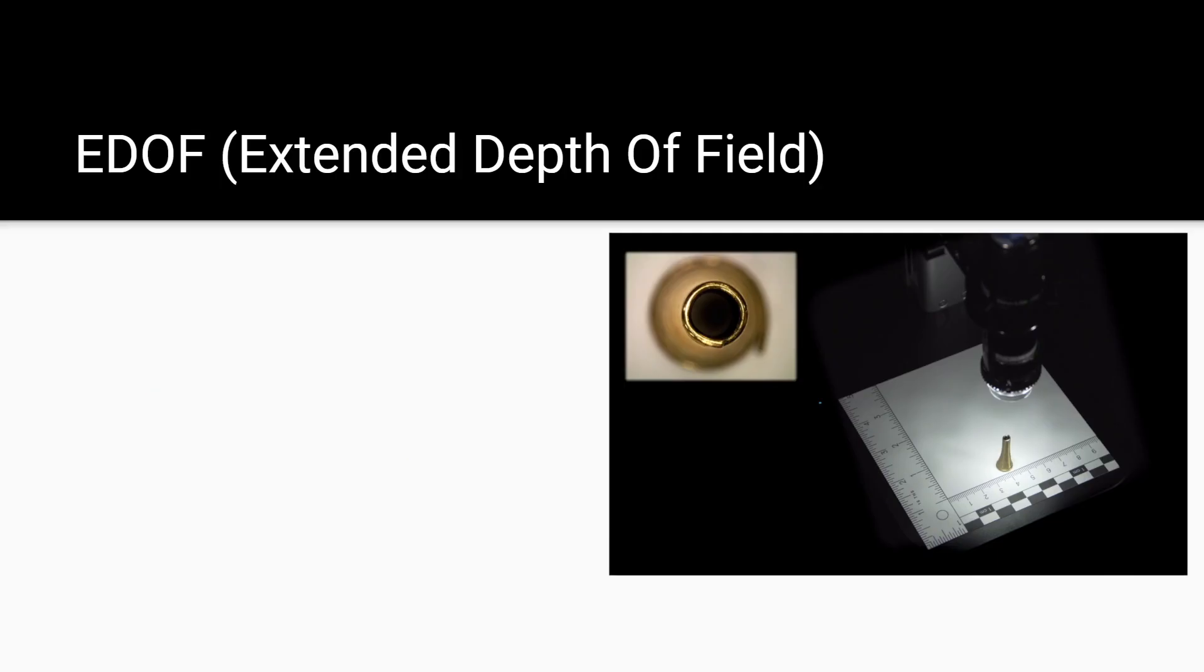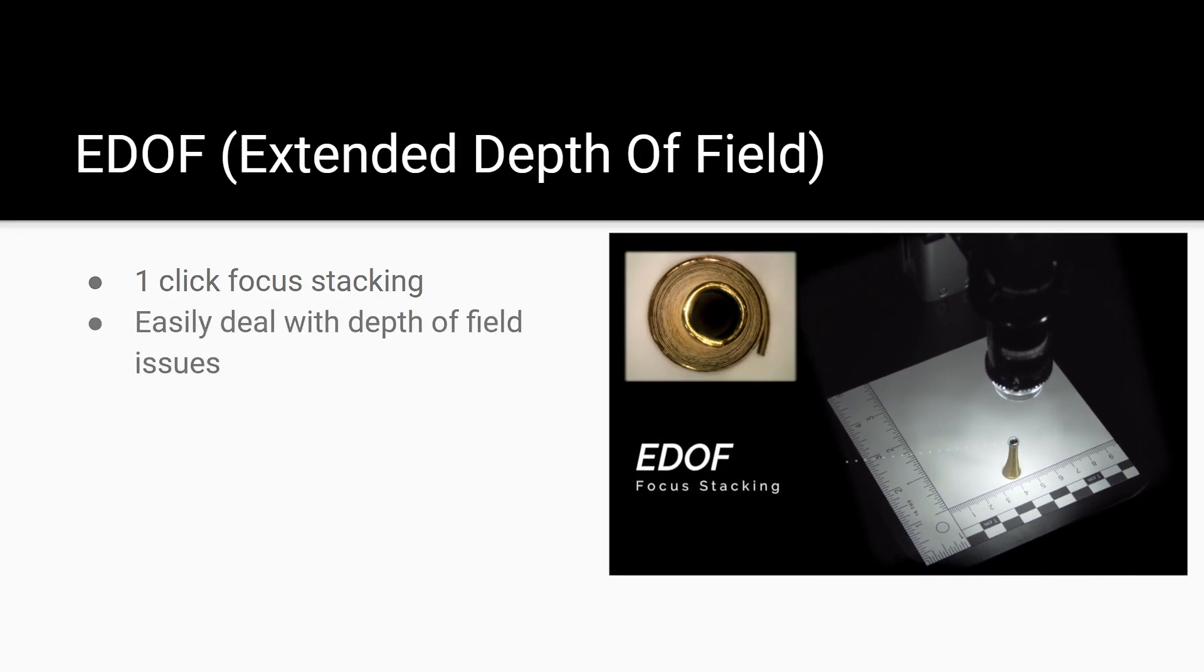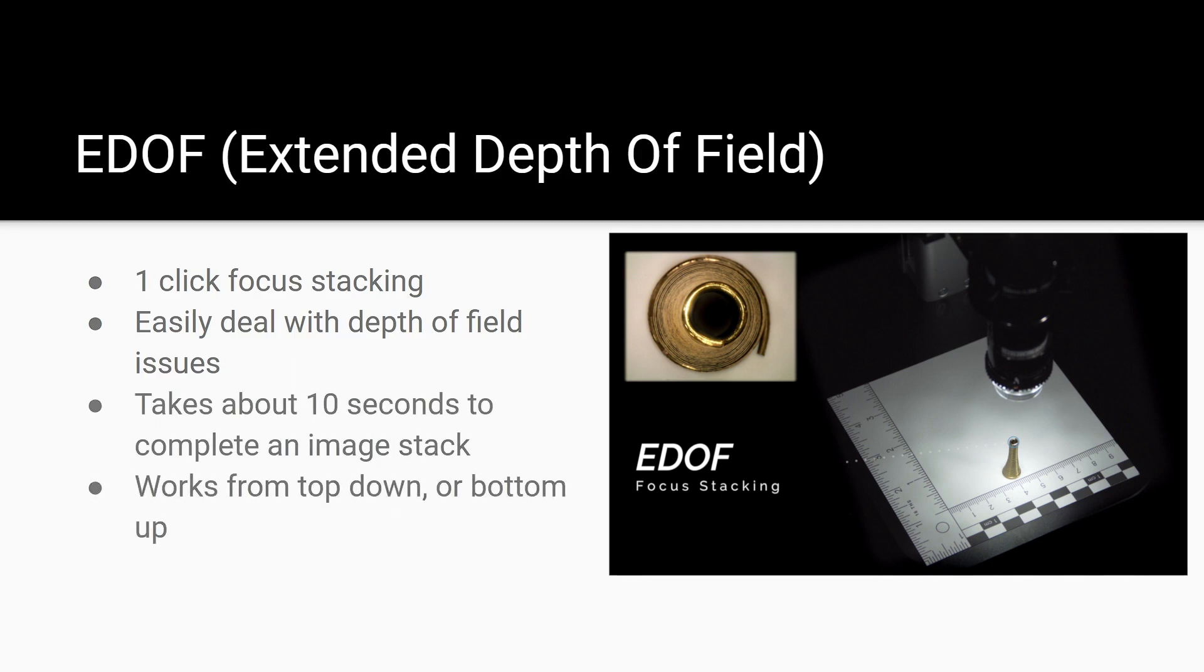The next special feature I would like to talk about is EDOF, or Extended Depth of Field. Models with this feature can perform one-click focus stacking, which allows you to easily deal with depth of field issues. This feature works by automatically capturing images from different focal planes and stitching them together. Once the different images are captured, you will have a composite image in about 10 seconds with everything in focus. This process can capture images from either the top-down or bottom-up.